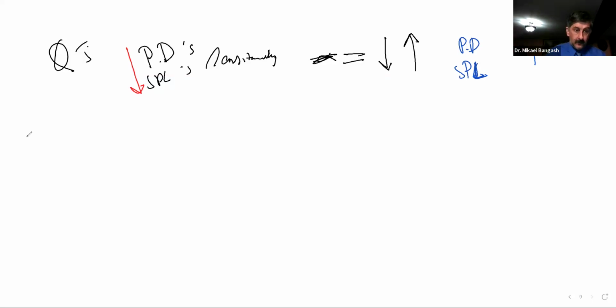Now, guys, you just have to look at what is the effect on sensitivity. Now, where do we have this? It was a reduced sensitivity because we had backing material, which gave us pulses with shorter durations and shorter spatial pulse lengths. Clear? Would it be the same to say that the sensitivity of this transducer would be the same as the sensitivity of these transducers with low pulse duration? No, they cannot be the same.